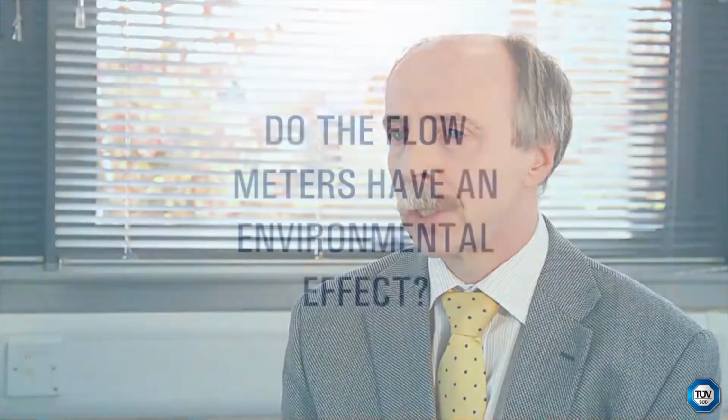Well, for example, can you actually break into the existing pipe run to install the meter at that location? And once you've got it there, what access do you have to that location for removing and replacing the meter subsequently, for maintenance, for calibration, or even to read the data if you don't have remote reading capability on the meter? We've spoken about the installation effects. So do you actually need to put flow conditioners in there? Have you got space at that location? And taking all of that together, what's the impact going to be on the uncertainty that you will achieve from that flow meter in that particular installation?